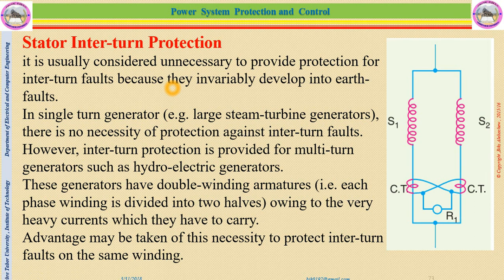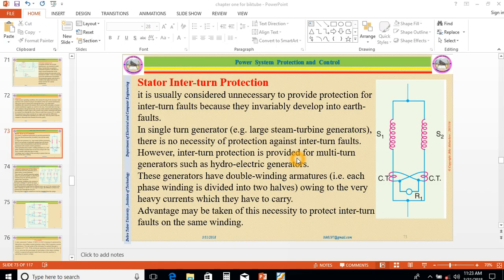Now let us see stator interturn protection. It is usually considered unnecessary to provide protection for interturn faults because they invariably develop into earth-faults. For example, in some generators there will be only a single turn. In a single turn generator, for example a large steam turbine generator, there is no necessity to protect against interturn faults, because interturn protection is provided for multi-turn generators like hydroelectric generators. In hydro generators, they may have more than two windings. So those generators have double winding.